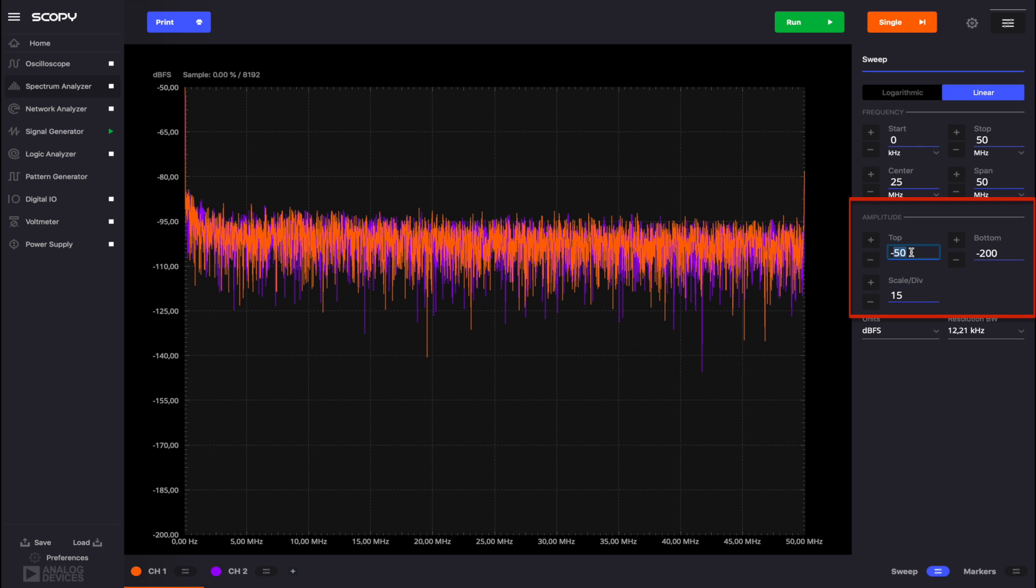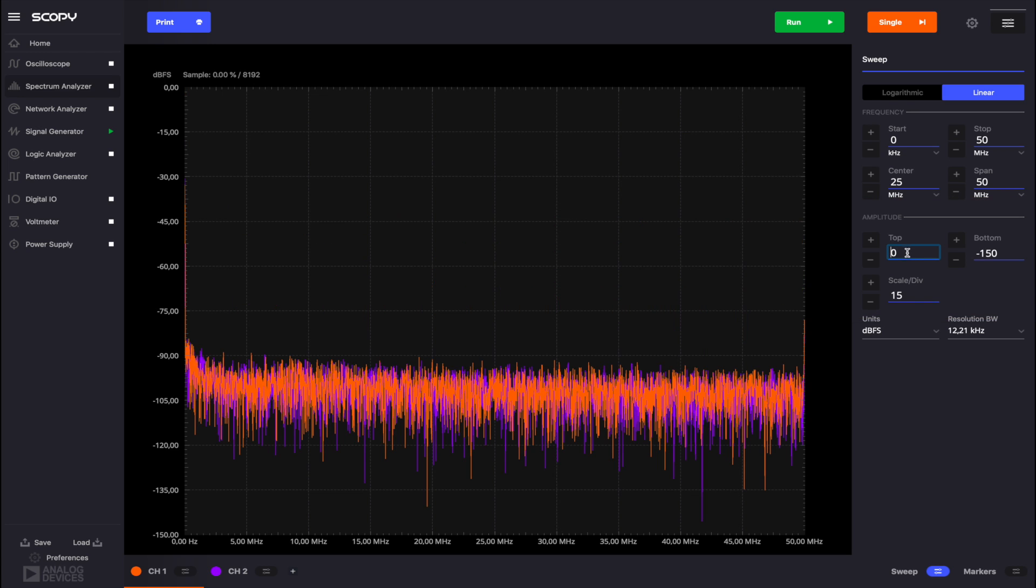The greater the number of samples, the more time it will take Scopy to plot the corresponding FFT. We'll keep the default option for units. The resolution bandwidth is set to 12.21 kHz. Set the scale to 15. Set the top amplitude to 0 and the bottom value will update based on the top one and the scale.